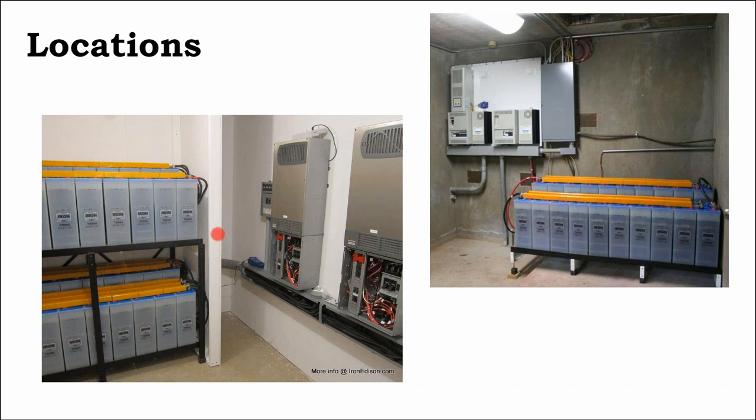What they've done here is they've said, okay, this is not enough space between the battery and the inverter, so we have to put a protective barrier, a wall, there. But of course, the problem is that gets you from a 4 foot spacing requirement to a 3.5 foot spacing requirement. And just to my naked eye, I don't think that's 3.5 feet. I think they recognize the safety hazard, so they put in a wall so someone standing here isn't backing into the electrical equipment, but they still didn't leave enough adequate space to work that area.